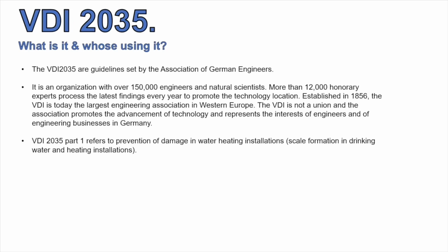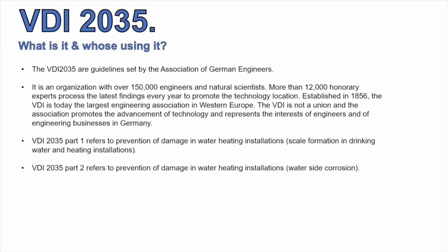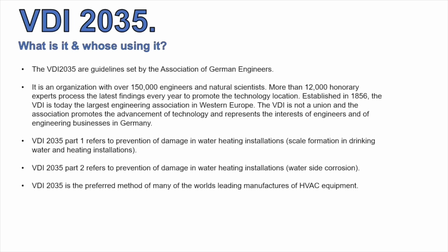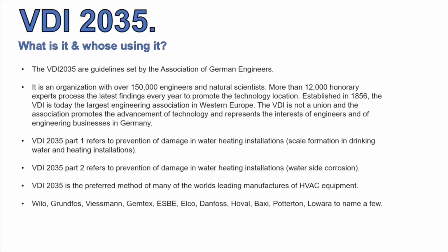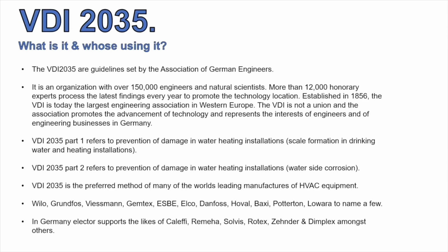VDI2035 Part 1 refers to prevention of damage in water heating installations, scale formation in drinking water and heating installations. VDI2035 Part 2 refers to the prevention of damage in water heating installations, waterside corrosion. There also is a VDI Part 3, but that refers to corrosion caused by gases in gas carrying systems. VDI2035 is a preferred method of many of the world's leading manufacturers of HVAC equipment. In Germany, Electa supports the likes of Caleffi, Remeha, Solvis, Rotex, Zehnder and Dimplex, amongst others.